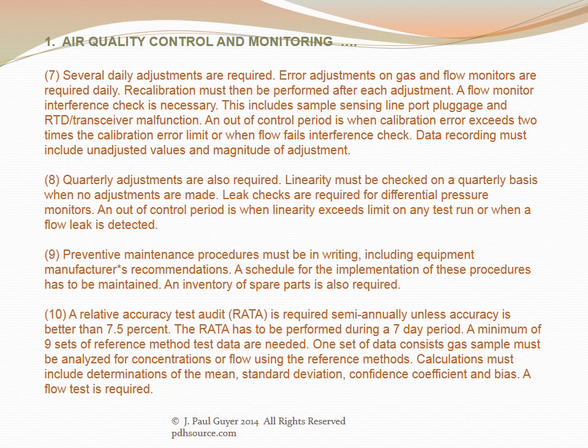Several daily adjustments are required. Error adjustments on gas and flow monitors are required daily, and recalibration must be performed after each adjustment. A flow monitor interference check is necessary, including sample sensing, line port plugage, and RTD transceiver malfunction. An out-of-control period is when calibration error exceeds two times the calibration error limit or when flow fails the interference check. Data recording must include unadjusted values and the magnitude of adjustment. Quarterly adjustments are also required; linearity must be checked quarterly when no adjustments are made. Leak checks are required for differential pressure monitors. An out-of-control period occurs when linearity exceeds the limit on any test run or when a flow leak is detected.